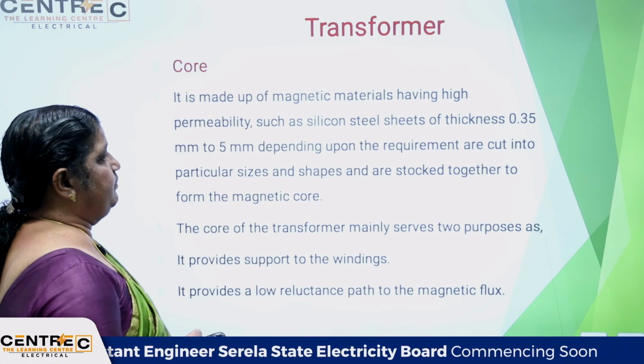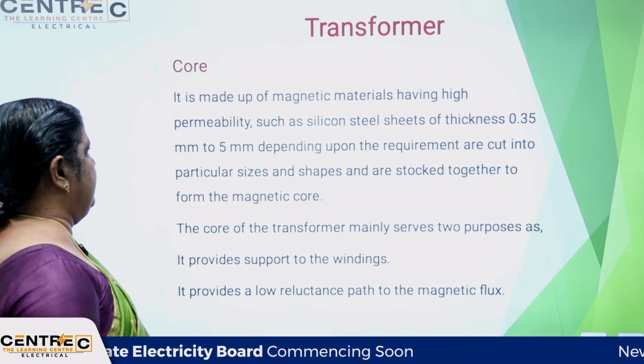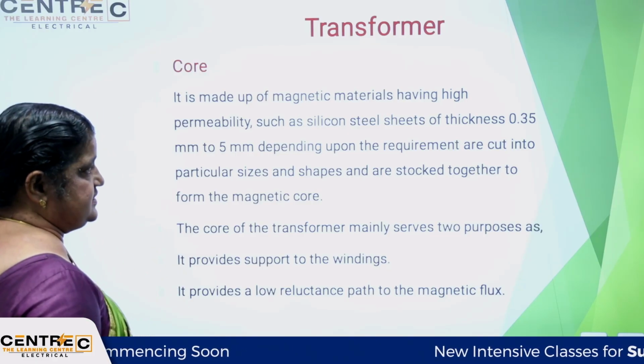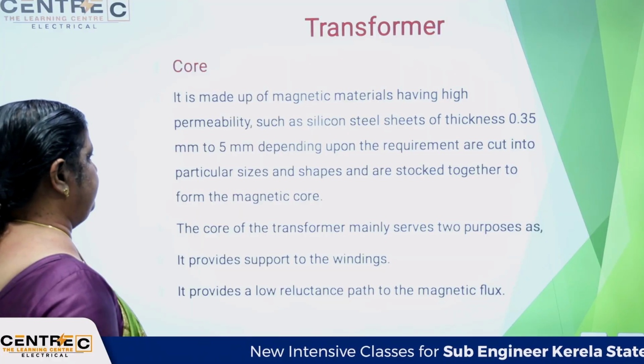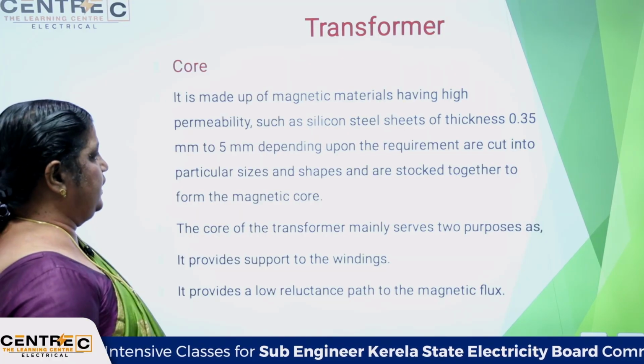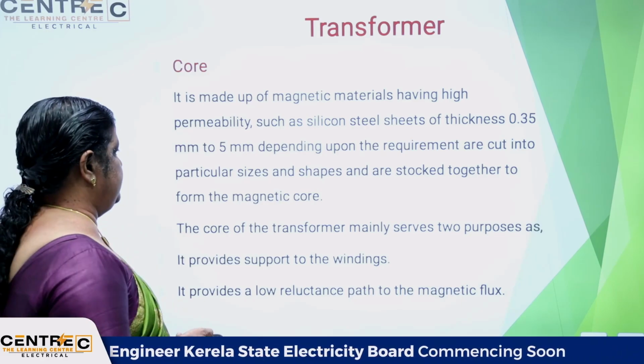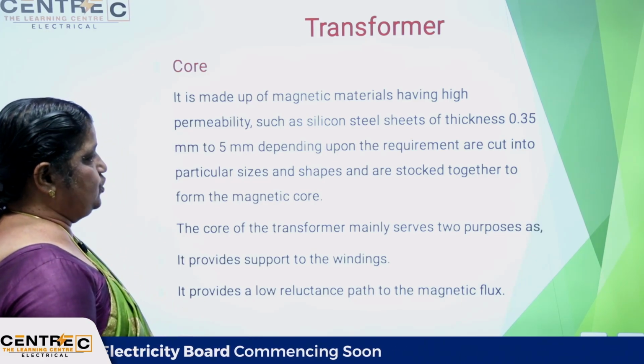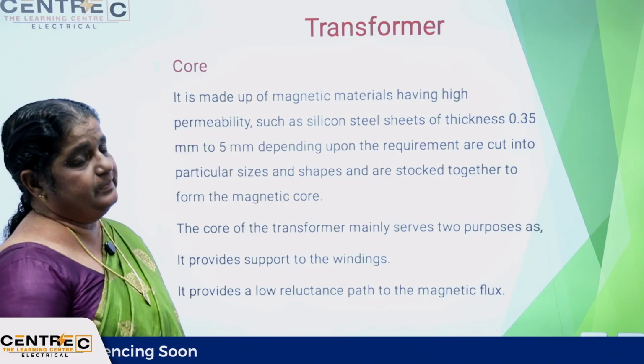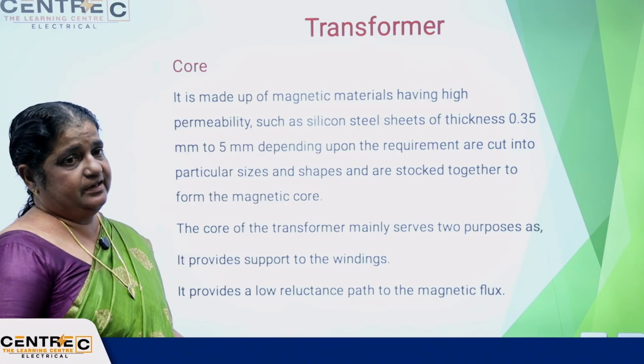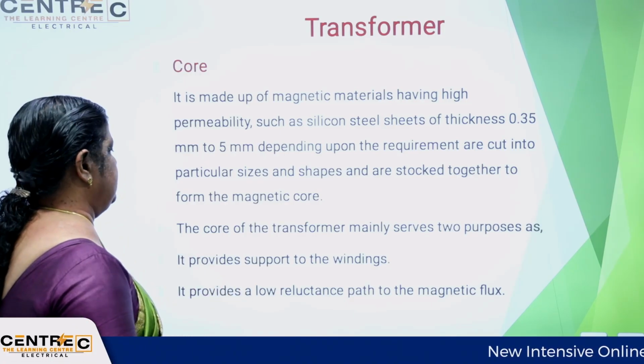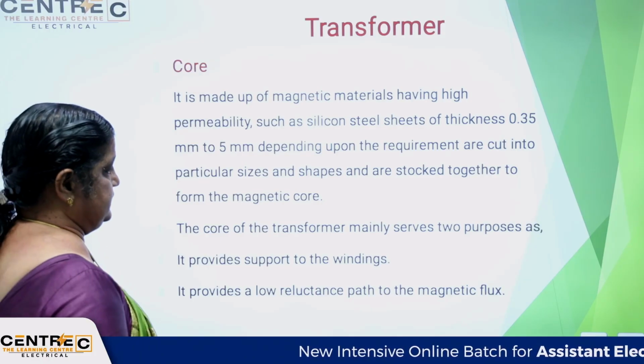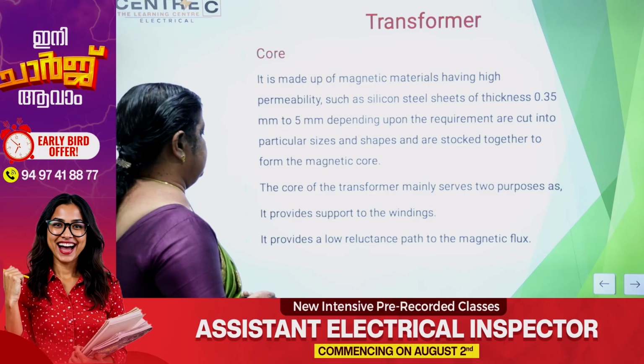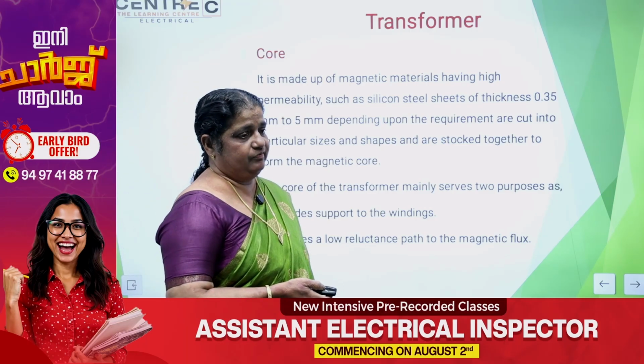Core: it is made up of magnetic materials having high permeability, such as silicon steel sheets of thickness 0.35 mm to 5 mm, depending upon the requirement. They are cut into the particular size and shape and are stacked together to form the magnetic core. It is just like a magnetic form, that is, a laminated core. The core of the transformer mainly has two purposes: it provides support for the winding and a low reluctance path for the magnetic flux. These are the functions of the core.